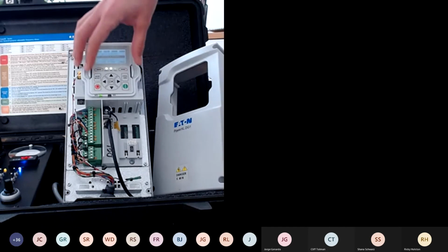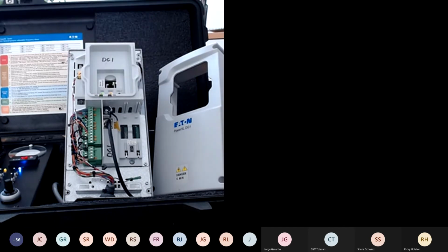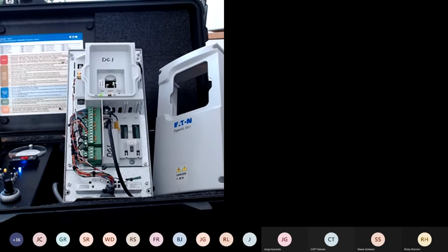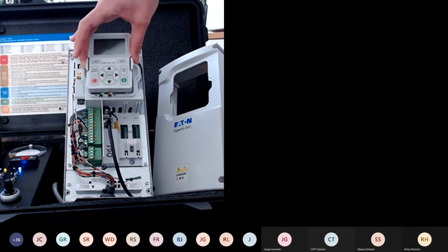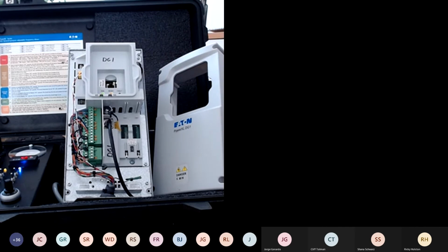and right now, since we have the drive in I/O remote control, I can actually remove the keypad and still have our machine continue working because all the control is being done remote. So as soon as I remove the keypad, you see that there is an additional Ethernet port right there onto the drive. So for this specific drive, this I/O port is actually helpful to be able to upgrade firmware and be able to connect onto your computer and change some programming. Maybe you want to do for certain drives a low temperature that could require reprogramming. And again, this keypad is where you would upload all your data, save as a backup so that you have a system backup. Or, like I'm showing here below, using the Ethernet or connect directly onto the drive and save the parameters and the programming onto your computer.